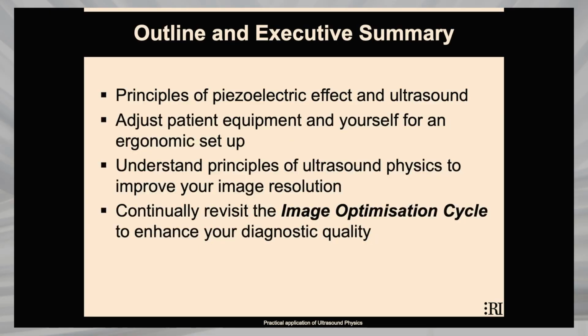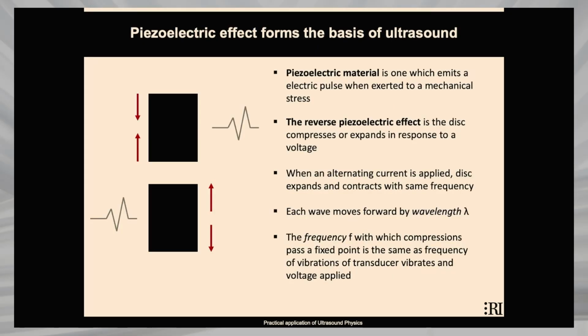But essentially, ultrasound is based on the piezoelectric effect. This essentially means that there are certain materials that, when you pass a current through them, will expand and contract, and that will emit a sound wave. If you have an alternating current, they will expand and contract with the same frequency. In addition, this can also act as a transducer in terms of receiving the signal. The frequency with which the compressions pass a fixed point is the same as the frequency of vibration of the transducer and is directly related to the voltage that's applied.